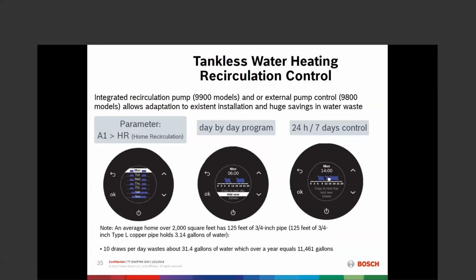Why do we want to do that? Two things. One, it's better energy efficiency. We really don't need the unit running nonstop to keep that domestic loop hot. So efficiency is one part of it, saving energy, which is one of the biggest reasons why people want tankless water heaters. The other reason is just longevity of the unit. If we let it run for 3.5 hours every morning, 365 days a year, that's a lot of additional wear on the unit and drives down the durability of the unit. So we want to make sure we're maintaining that durability.